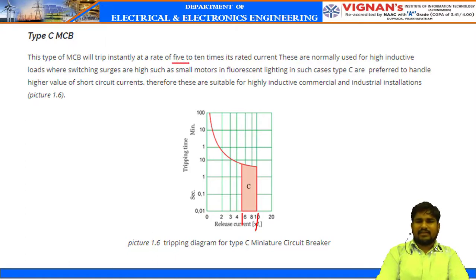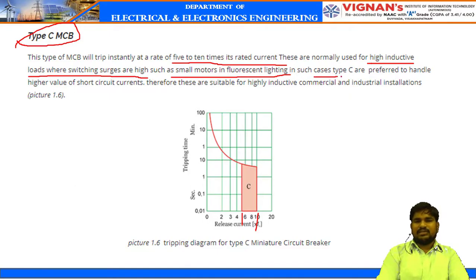type C MCB will be used. This is used for high inductive loads where the switching surges are high, like small motors or fluorescent lighting. In such cases type C is preferable to handle higher values of short circuit current. So these are used in highly inductive commercial or industrial applications.